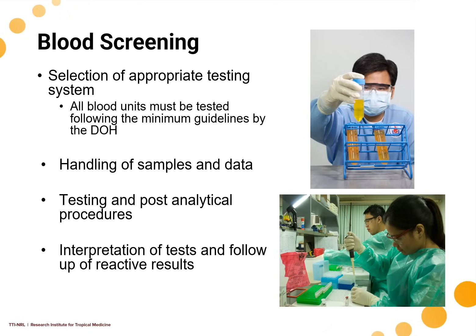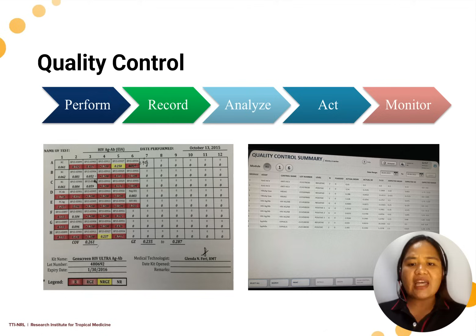And in terms of quality control, we need to also have QC for reagents, and this should be performed every batch run. You must record this, analyze, and act if there are deviations, and monitor your QC as well. Check for shifts and trends. So when doing Levey-Jennings chart, look out for possible shifts and trends. Do not release out of control runs. You need to identify root causes for any out of control runs and troubleshoot them before proceeding to retesting a batch. Monitor these errors and have corrective actions to prevent them from happening again.